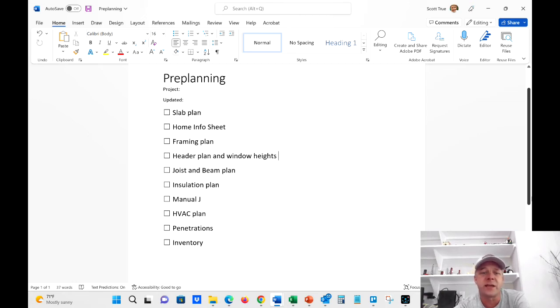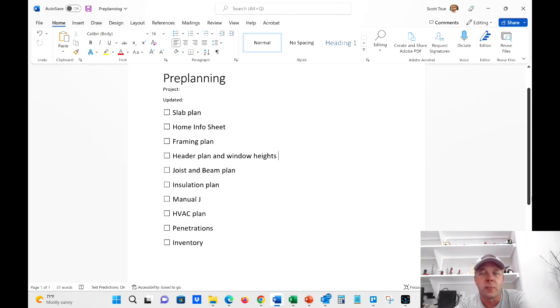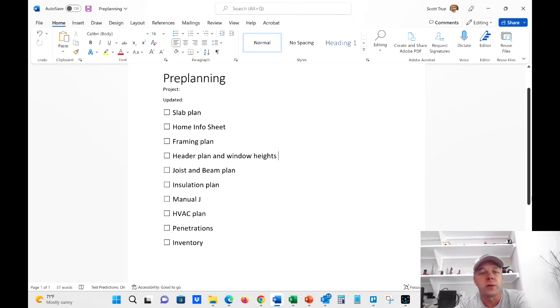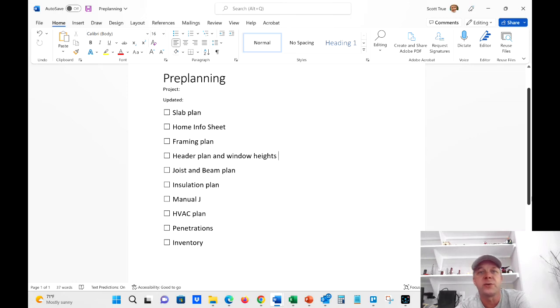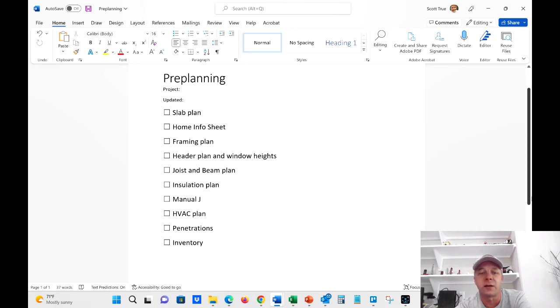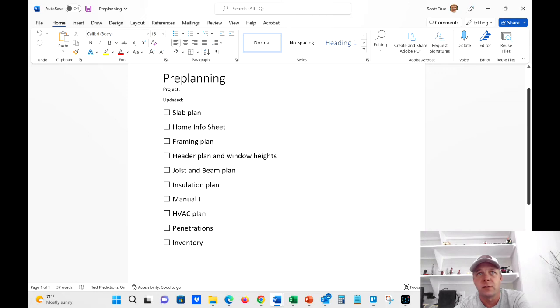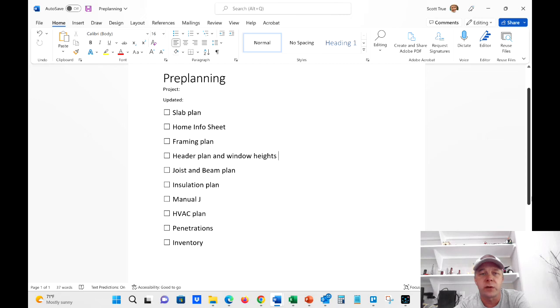So next thing is the HVAC plan. Or sorry, manual J first. So usually I'll go ahead and get the manual J done. And so that we know what is the load of the house. And then from there, we'll do the manual S. It's not written here, but we'll go ahead and do the manual S and then the manual D. So which is the selecting of the equipment and then the duct design. So we'll get all that done. And so before we build, we know what machine we're going to put in there, how it's designed, what's going where.